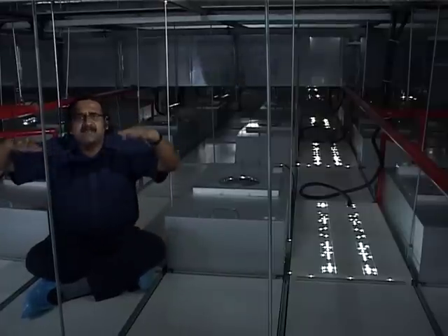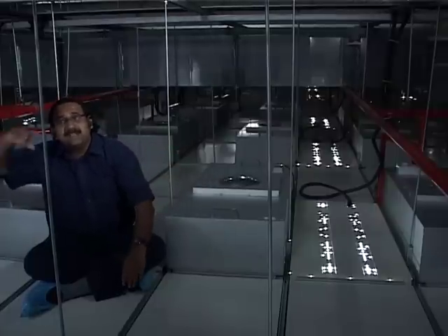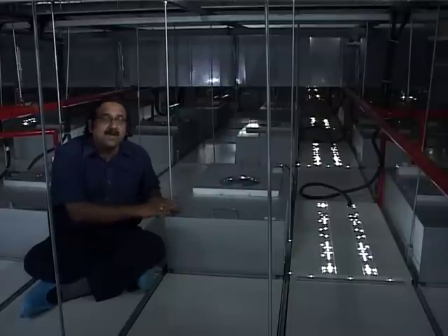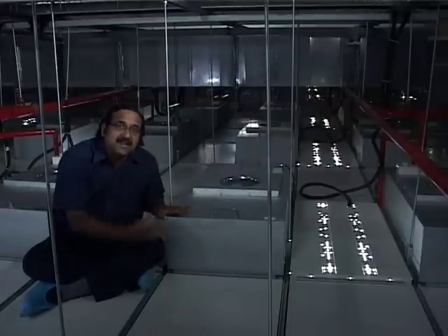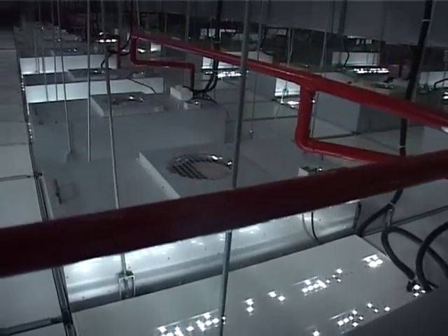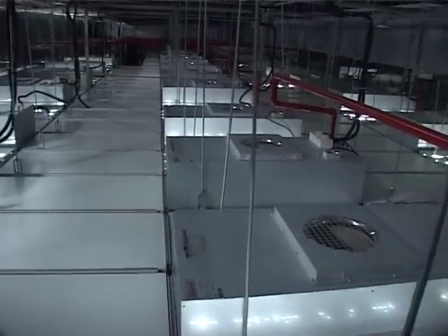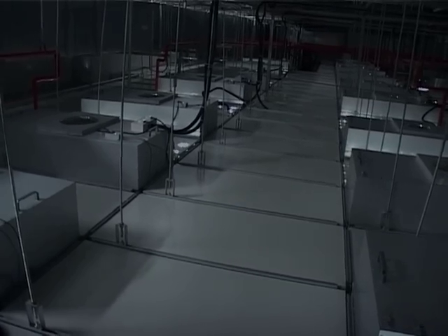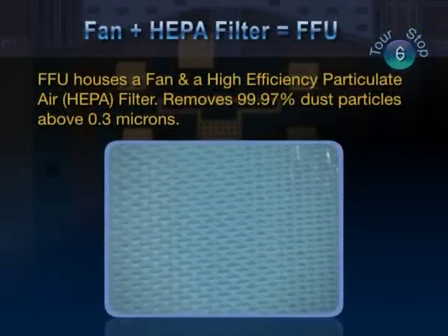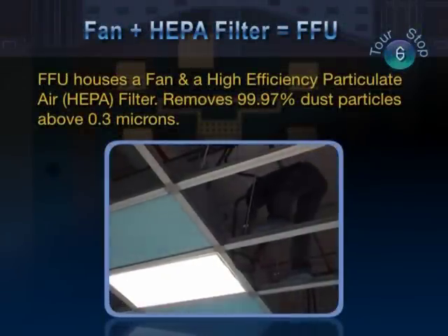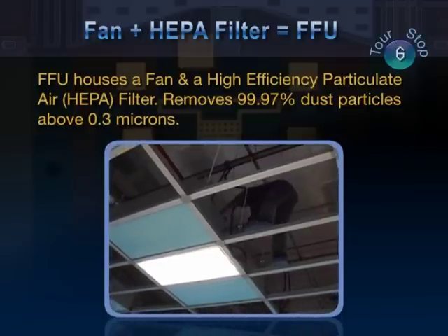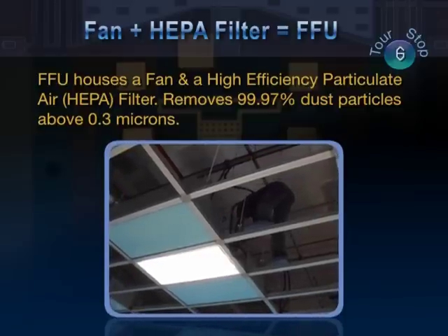Now you can see that there will be many dust particles floating around here, and these particles will be removed by this fan filter unit when the air enters the clean room. Thus, we maintain the required cleanliness within the clean room by a series of fan filter units sitting in this plenum area. The fan filter unit is made up of a fan and a high-efficiency particulate air or HEPA filter. These remove 99.97% of dust particles with diameter above 0.3 microns.